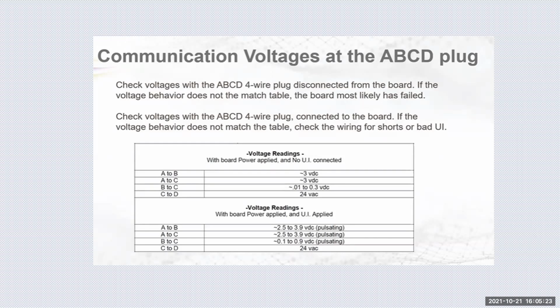Another thing to check, especially if you're going back on a follow-up of another tech that couldn't figure this out, make sure that those wires are still A to A, B to B. I get it a lot that guys will be fighting this, and I'm like, check your wires, and they've been crisscrossed, A to B and B to A. Make sure A is to A, B is to B. If all's good there, your joints are good, you're not crossed anything, and you go outside and you still have 0.02, time to pull a new wire.